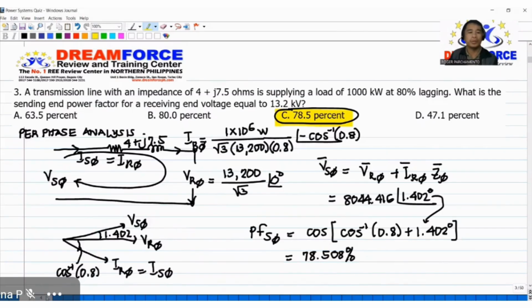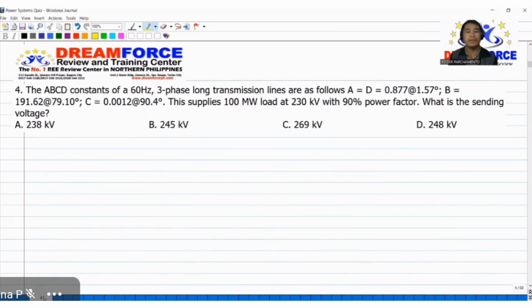Number 4. The ABCD constants of a 60 Hz three-phase long transmission line are as follows. A and D, 0.877 at 1.57 degrees. B is 191.62 at 79.10 degrees. And C is 0.0012 at angle 90.4 degrees. So this supplies 100 megawatts load at 230 kV with 90% power factor. What is the sending end voltage?